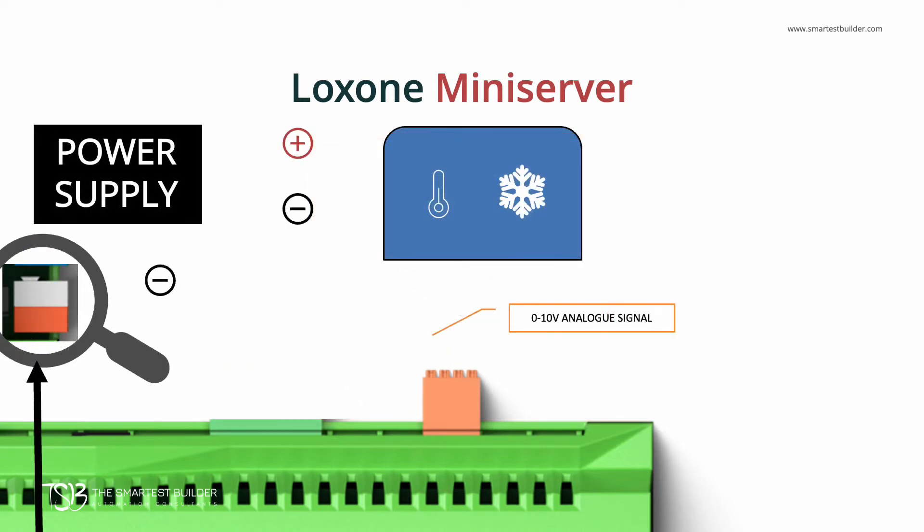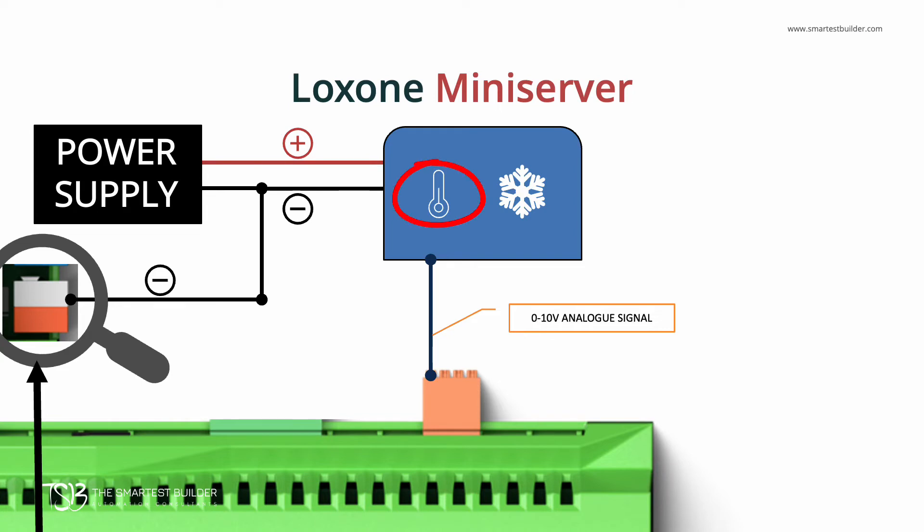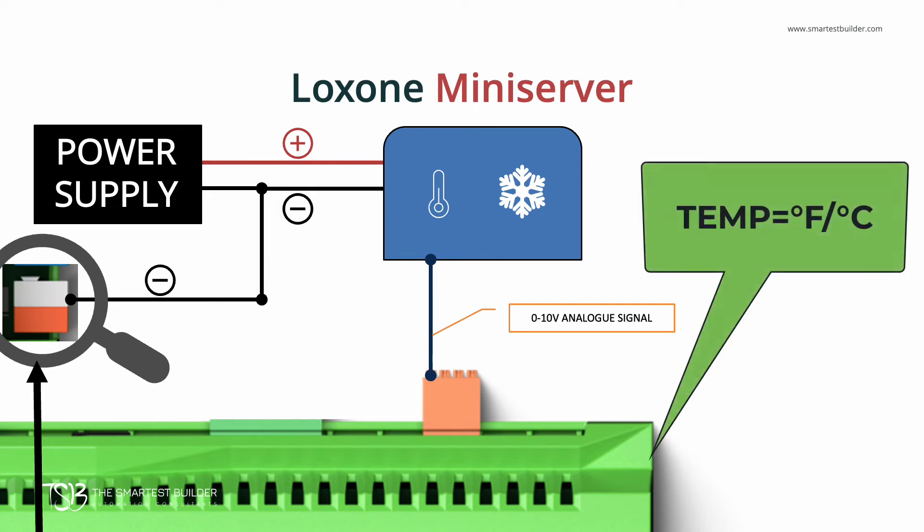Now let's look at an analog input example. In this example, I've used the analog input to tell us the temperature of a freezer. The probe that's in the freezer sends an analog temperature value to a transmitter, which converts that value to a 0 to 10 volt analog signal. This signal is then transmitted to the Mini Server's analog input, where the voltage is read and then converted in the Loxone Config software to a digital temperature value.